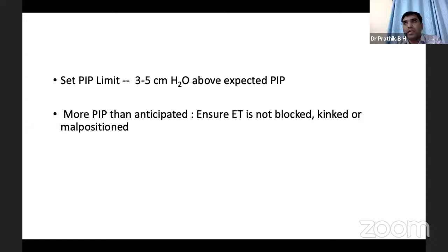For example, if the expected PIP required for the baby is around 16 centimeter of water, then you can set a PIP limit of around 19 to 20 centimeter of water. If more PIP is required than anticipated, then you have to make sure that the endotracheal tube is not blocked or kinked, or malpositioned in the right bronchus.